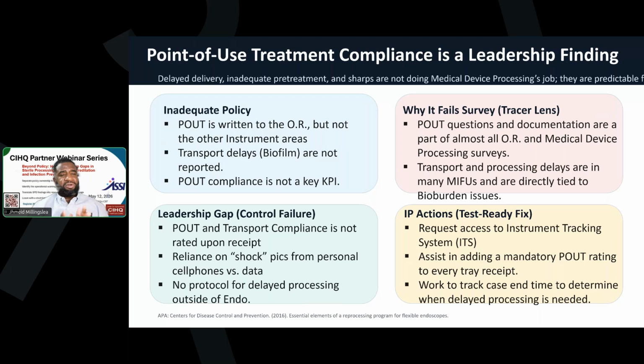We also don't address transport delays outside of endo. Like if we have endo, if you get outside that hour, you have to do enhanced processing. And you go, yeah, that makes total sense. Why don't we do enhanced processing when we have those long delays in the operating room? Same theory, biofilm forms on top of biofilm, on top of biofilm. I saw an interesting presentation at HSPA about how sometimes when you get rid of biofilm, that was the biofilm that was covering up the other layer of biofilm, right? And a lot of times we don't treat point of use compliance as a key performance indicator.